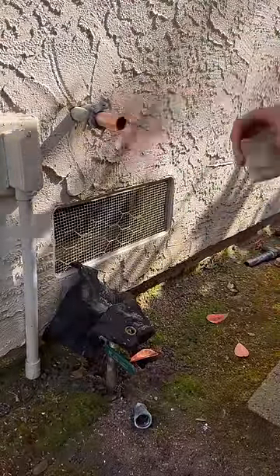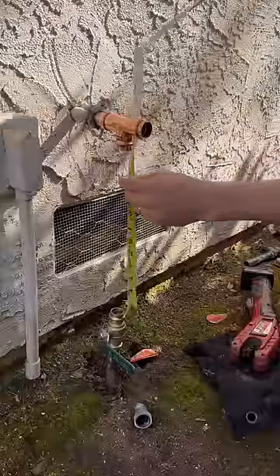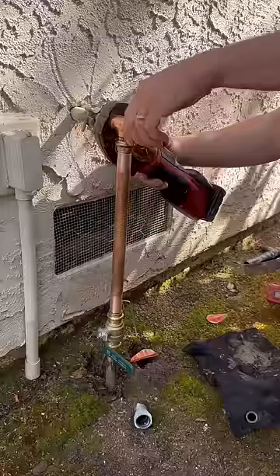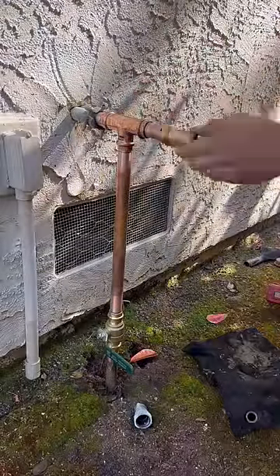I use an inside/outside barrel reamer — sometimes it gets the inside of the pipe on one end and the outside on the other. It's recommended to deburr the outside whenever using a press fitting, that way you don't cut the o-ring when the pipe is inserted.